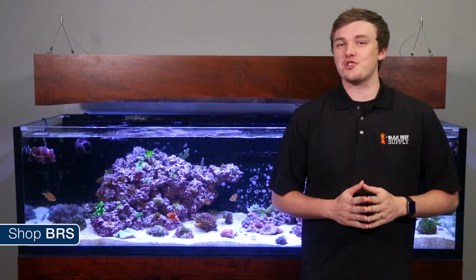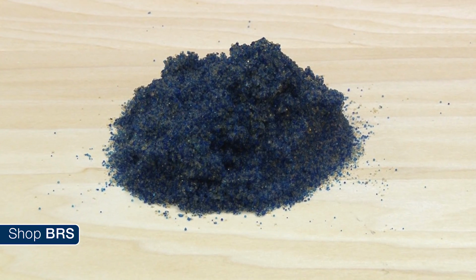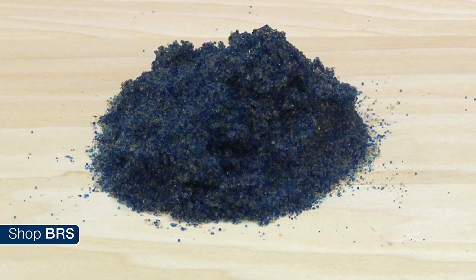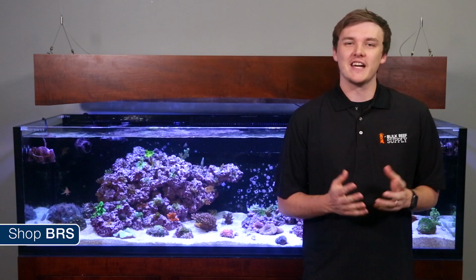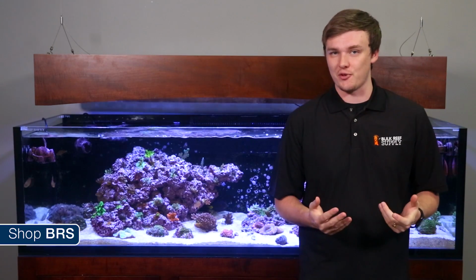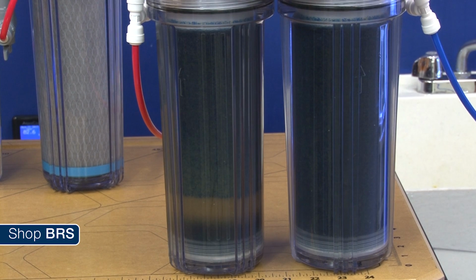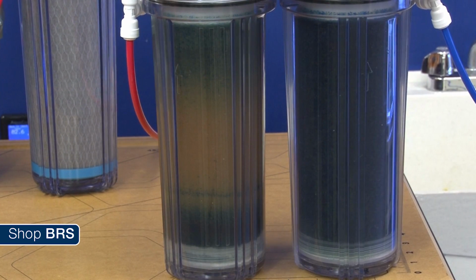The one exception to this rule, however, is deionization resin. DI resin is a mixed bed, which means it contains cation and anion resins, each with their own distinct charge, whether it be positive or negative. Contaminants that often show up as TDS are reduced as they bond to the surface of the resin. As the resin is depleted, the TDS will rise in tandem with a handy color change, alerting you that it's time to replace the media.